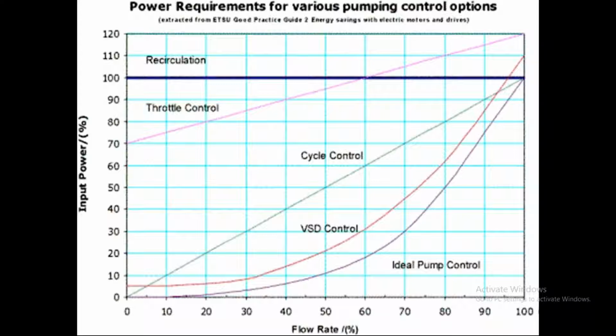So why is this VFD put on a blower? When the blower is put to recirculation, straight away 100% is the consumption. There is no energy saving here. Whereas if the blower is throttled by a damper control at the delivery of the blower, 70% consumption is there. If it is put on cycle control, switching on and off, that is the best way of control, like what we do in our domestic fridge.